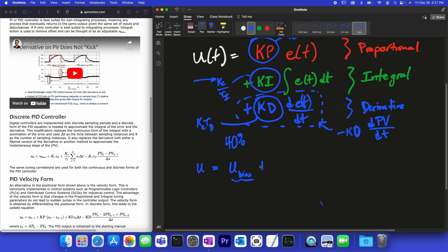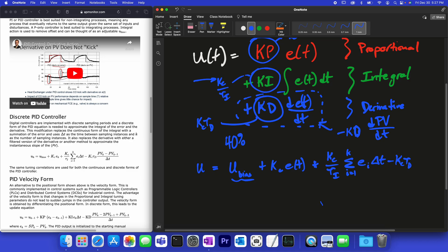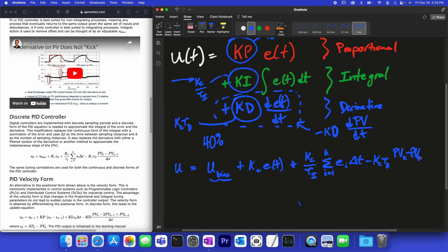Then we add kc times the error, plus kc over tau_i times a summation from i=1 to k of error times delta_t (that might be one second). And then minus kc times tau_d times a finite difference of the PV: (PV_k minus PV_{k-1}) divided by delta_t. That gives us our discrete derivative term.